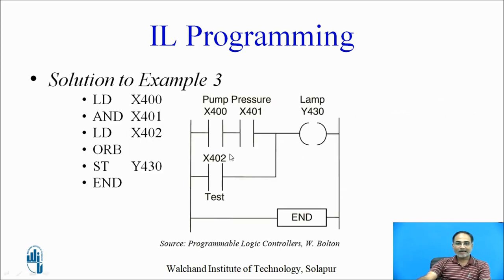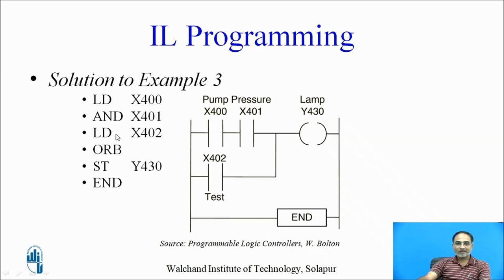The ladder diagram shows the pump and pressure sensors in series, with a test switch in parallel, driving a lamp output. In the Instruction List: LD reads the pump sensor status, AND combines it with the pressure sensor, LD reads the test switch, ORB combines the two blocks, and finally ST Y430 writes the result to the lamp output.